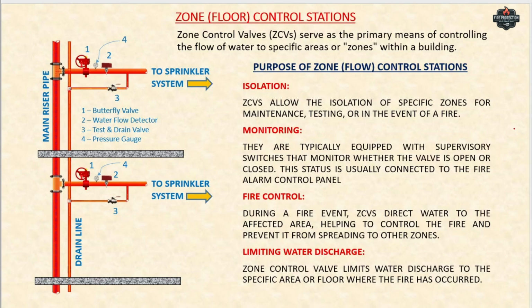A zone control valve or a floor control station is basically used to monitor the sprinkler system across different areas or zones of a building, like on the first floor, second floor, or in the basement we have multiple zones, zone 1, zone 2, like that. It allows us to isolate specific sections of the sprinkler system, making it easier to perform maintenance without disrupting the entire system. Like here, you can close one valve and do the maintenance and then open the valve again. So it will not affect the other areas. They control the flow of water to different areas of the building.